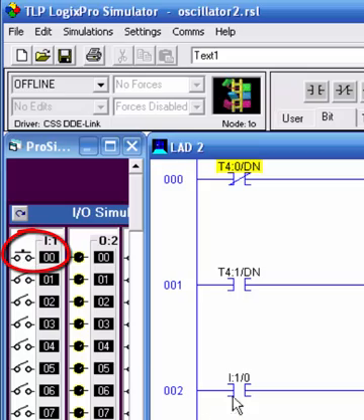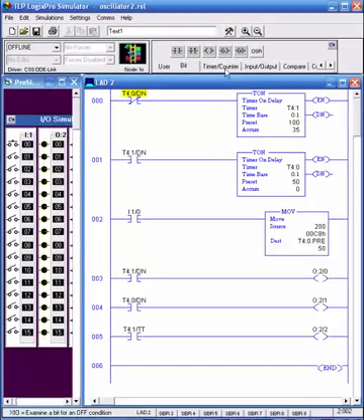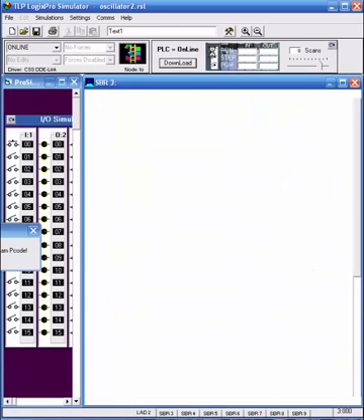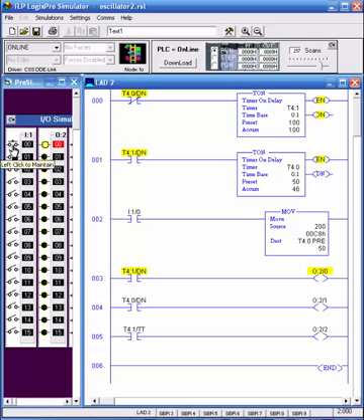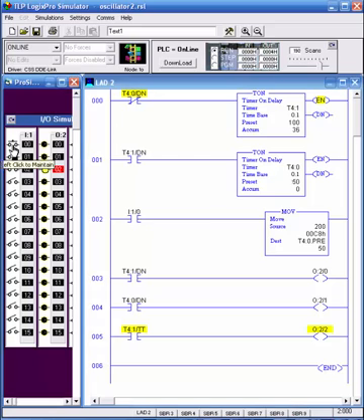I don't want this executed every time - maybe only when somebody pushes a pushbutton. So I'll add an XIC for input I:1/0, which is this pushbutton. When I push that button, I'll load 200 into the preset. Let's give this a shot: download, and things are oscillating with preset at 50 (five seconds). When I push the button I'll dump 200 in there instead - now it's going to have a much different duty cycle.